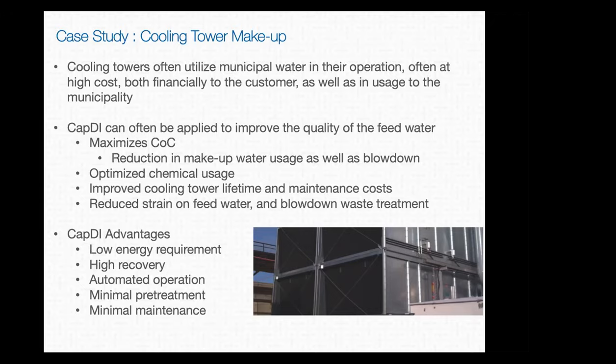So CAPDI here can be utilized on the makeup water to the system to treat the water coming in. It will improve the quality by reducing the TDS of that feed water, enabling that water to be cycled up more times than previous, so that it's making better use of that water, running the cooling tower more efficiently, and then allowing them to use less chemical, because when they're putting chemical into the cooling tower to prevent any corrosion, by blowing it down at a low number of cycles of concentration, they'll lose that water, so they have to replenish the chemical as well as the water.